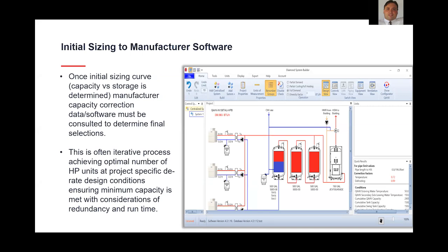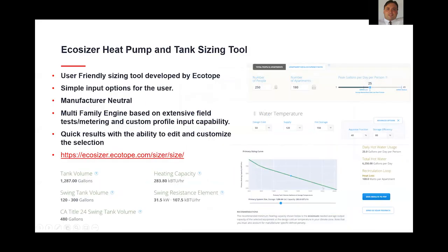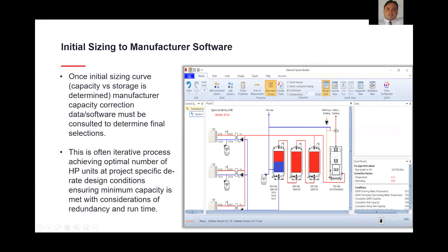So Mitsubishi has a software like this. It's called Diamond System Builder. This is also available to the public. You could go to our site and obtain that. And once you have that information in terms of storage volume, what you're going to store at, temperature, and the minimum output capacity you need, from this sizing type curve, you can bring that data back, and this software will provide the recommended number of heat pumps and storage tanks, at least based on our offerings, that would meet that load requirement. So that's kind of the process that you have to go through and think about.